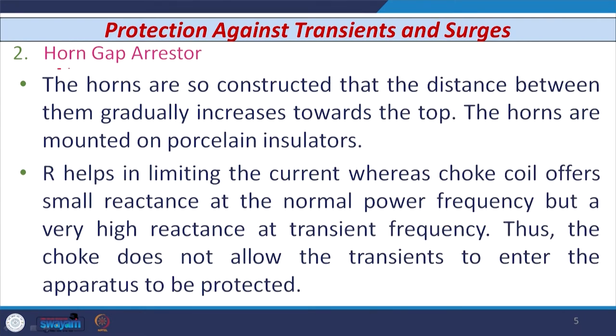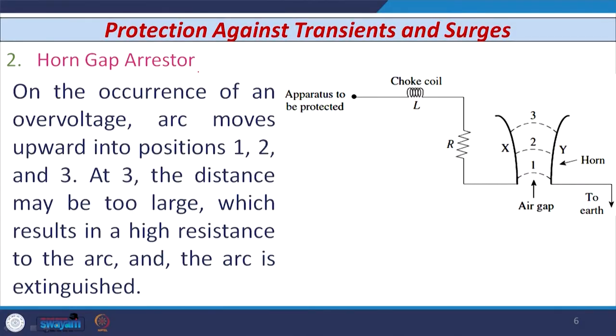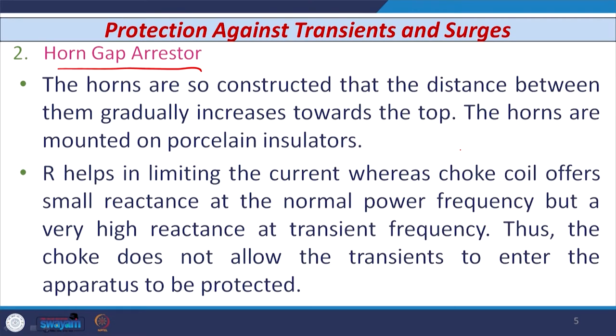The second type is the horn gap arrester. As the name suggests, it contains horns constructed so that the distance between the horns gradually increases towards the top. The horns are usually mounted on porcelain insulators. In the circuit, the apparatus to be protected is connected at one point and the other point is earth. A choke coil and a resistor R are also connected. The resistor R acts as a current-limiting resistor, while the choke coil offers small reactance at normal power frequency but very high reactance at transient frequencies.